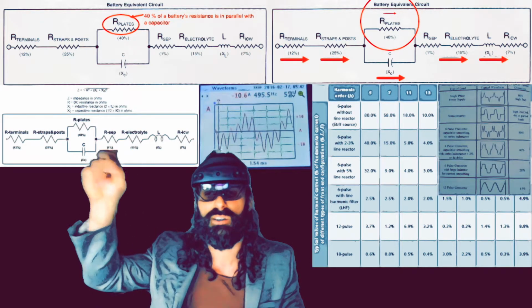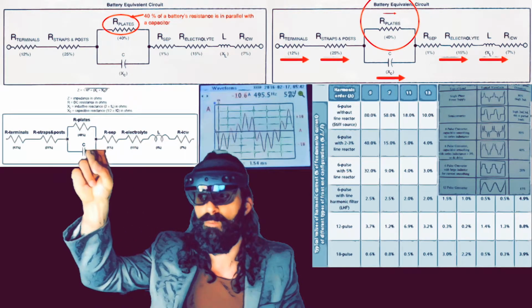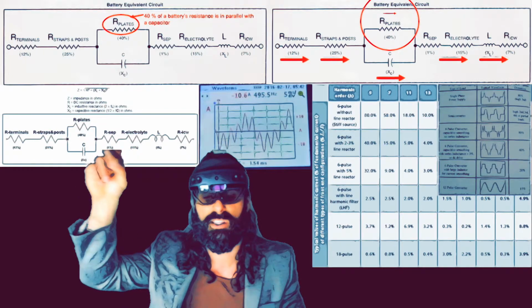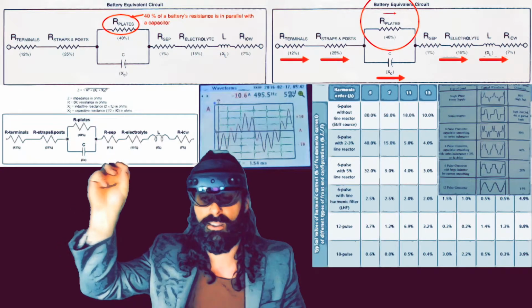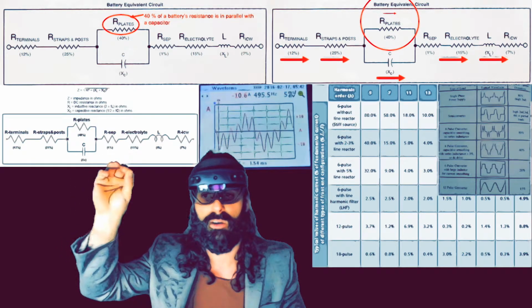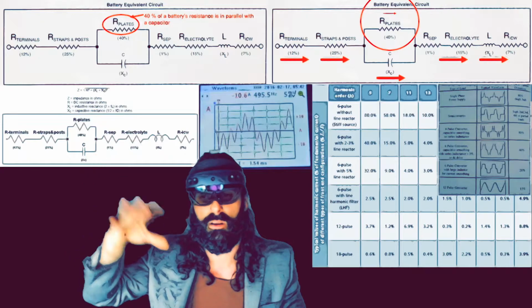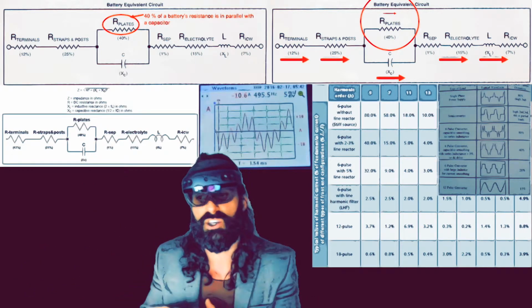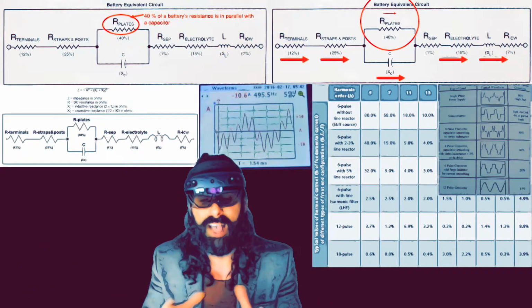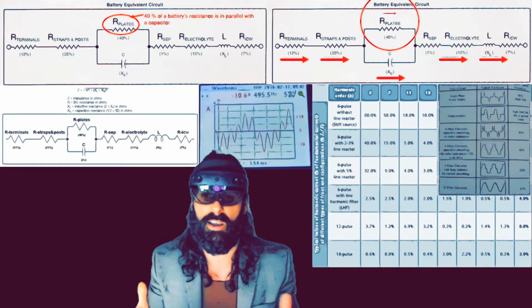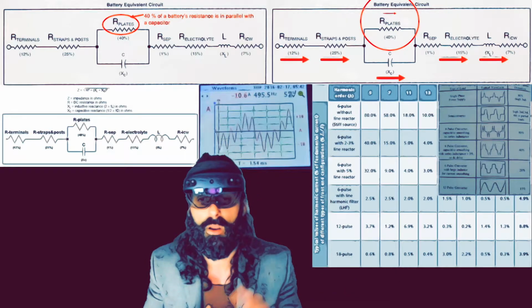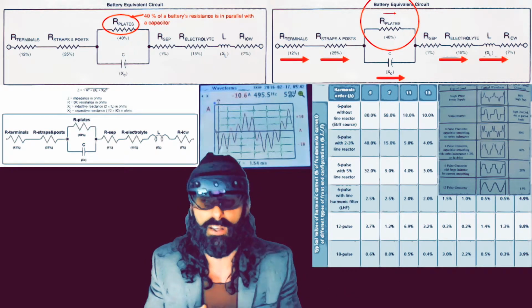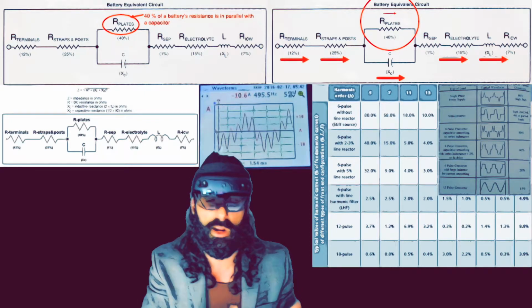Okay, so when you're strictly using DC, a purely resistive load, it bypasses and ignores the capacitive reactance of the battery. This is a huge deal, and it's significant because on larger battery systems this is essentially ignoring all of that, which can drastically interfere with the resolution of the device, and we'll get into that as we get into harmonics later, when we talk about 6 and 12 pulse rectifiers and inverters, and insulated gate bipolar transistors versus silicon controlled rectifiers.